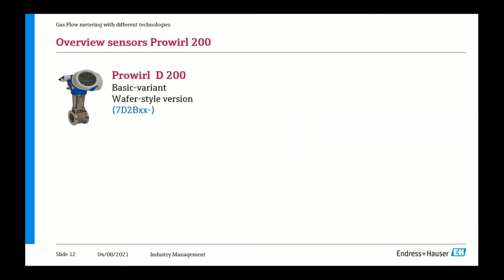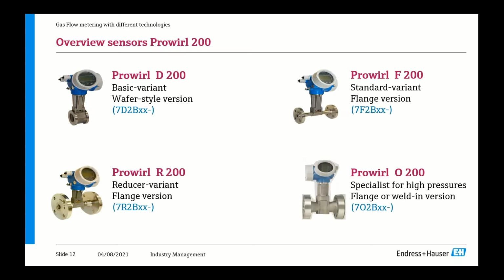So from our side, that's the Prowirl 200, and we have four different versions available for that. So we have a wafer version, so that is mounted between flanges. That's the Prowirl D200, D for disk. Prowirl F200 is the standard version in the oil and gas industry, so especially in the petro industry, refineries, you find this guy quite a bit. Sometimes you have to reduce the line size. The Prowirl R200 can do so up to 2 steps, so you can reduce from a 2-inch to a 1-inch version integrated in that device. And last not least, for high pressures, especially in the oil and gas world, we have the O200 up to class 1500. So also available as a weld-in or butt weld version.